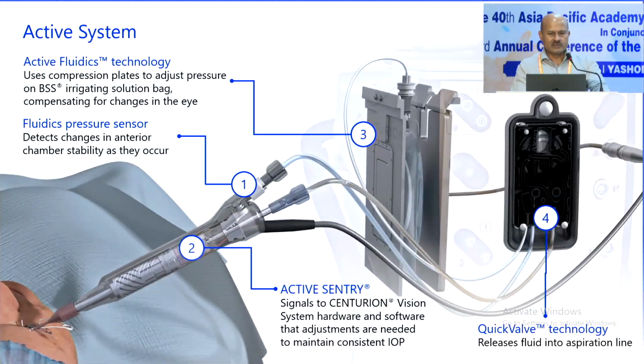So coming to the basics, what is the feedback, how the chamber is maintained. You see, number one is the fluidic pressure sensor directly in the handpiece, which monitors the intraocular pressure during the surgery. Then it gives feedback to two other systems. Two is the processor inside the machine, which gives commands to the active fluidics technology. Normally the infusion is gravity driven in the older machines, but here it is a compression plate. Depending on the feedback from the sensor, that is one, and the microprocessor, two, the pressure on the bag is modulated so that the infusion into the eye is maintained and the IOP is maintained.